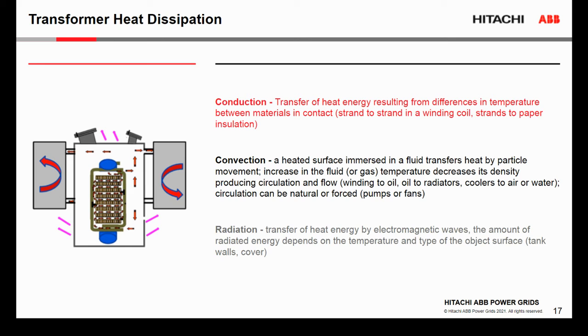Dissipation of the heat in the transformer. We have conduction, convection, and radiation. So with conduction, let's say we have inside the disc or inside the turn, the conductor, which inside has usually much higher temperature, and due to the difference in temperature between the turns, or between the turns and the insulation, we have heat transfer. The heat energy is transferred from the conductors which have higher temperature to conductors which have lower temperature.